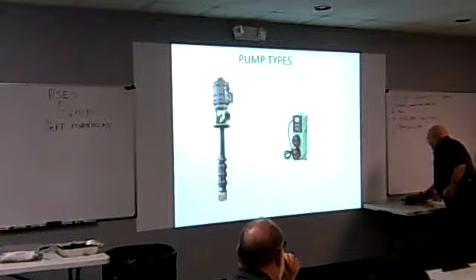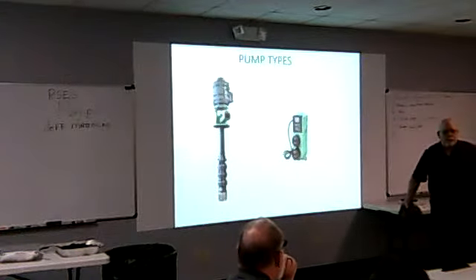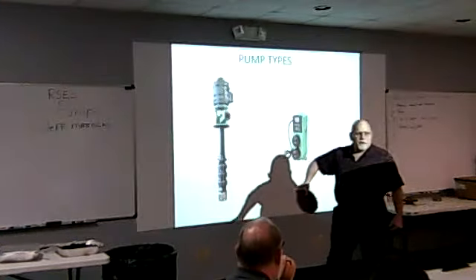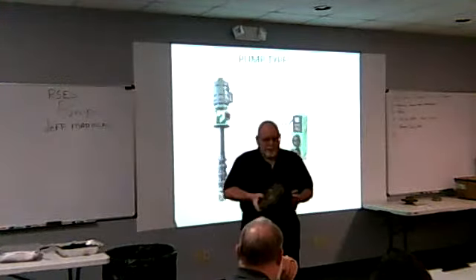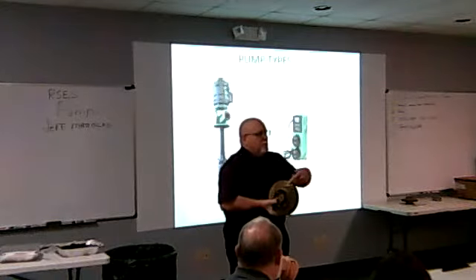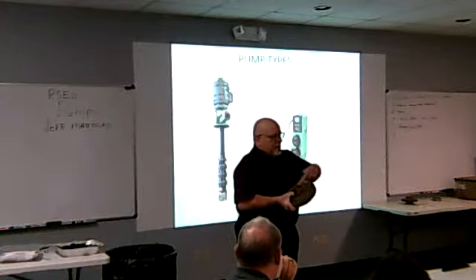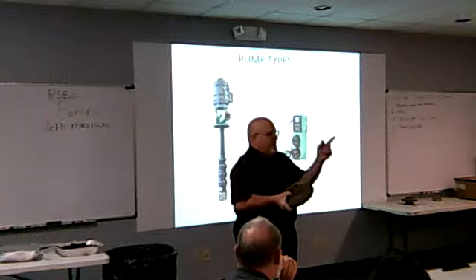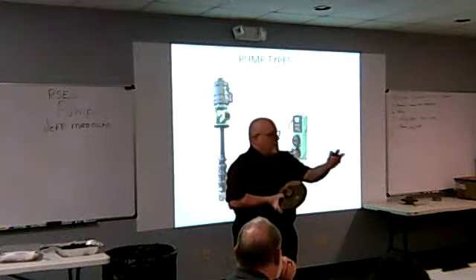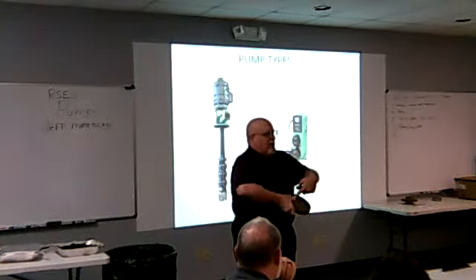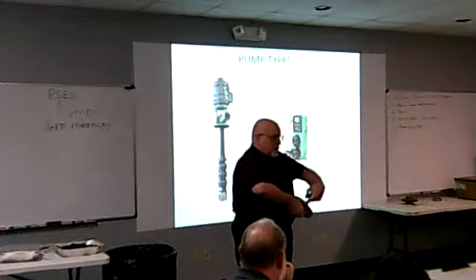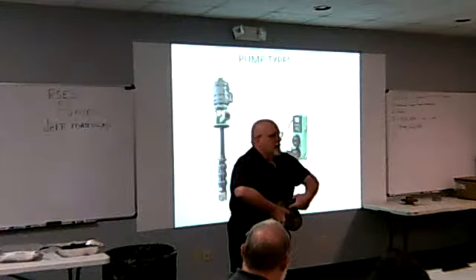This is an impeller out of a standard pump. And what you have here, this is called an enclosed impeller. And the reason it's enclosed, you see that these are on both sides. There's an open impeller, picture this piece off, it would just have the vanes. So this can get clogged, but the open vanes can't. This is called the eye. Remember that end suction pump? I told you the flow's coming in. The flow is going to come right in here.